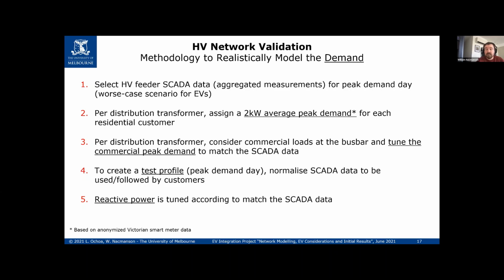So in this case, from the anonymized Victorian smart meter data that we have from previous projects, we know that around 2 kilowatts is a realistic peak. So that's our residential demand within the HV-LV feeder accounted for. And then we have this commercial component of load, which we don't know exactly what's going on there. You can have commercial customers of all sorts of different sizes.